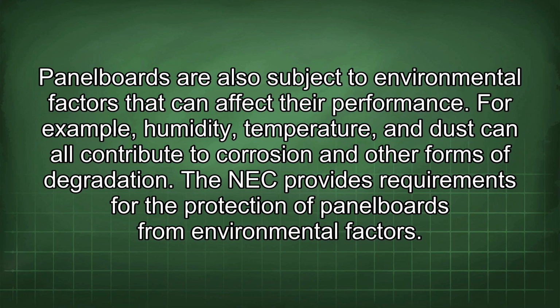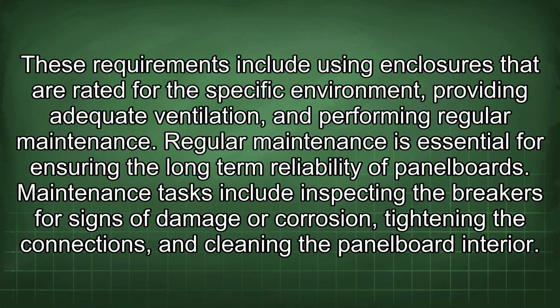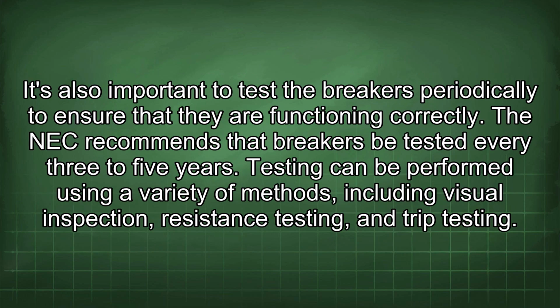Panel boards are also subject to environmental factors that can affect their performance. For example, humidity, temperature, and dust can all contribute to corrosion and other forms of degradation. The NEC provides requirements for the protection of panel boards from environmental factors. These requirements include using enclosures that are rated for the specific environment, providing adequate ventilation, and performing regular maintenance. Regular maintenance is essential for ensuring the long-term reliability of panel boards. Maintenance tasks include inspecting the breakers for signs of damage or corrosion, tightening the connections, and cleaning the panel board interior. It's also important to test the breakers periodically to ensure that they are functioning correctly.